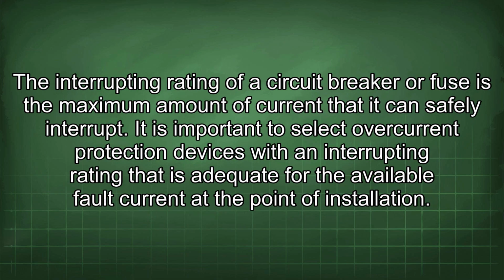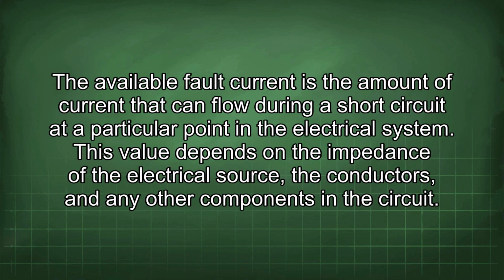The interrupting rating of a circuit breaker or fuse is the maximum amount of current that it can safely interrupt. It is important to select overcurrent protection devices with an interrupting rating that is adequate for the available fault current at the point of installation. The available fault current is the amount of current that can flow during a short circuit at a particular point in the electrical system. This value depends on the impedance of the electrical source, the conductors, and any other components in the circuit.